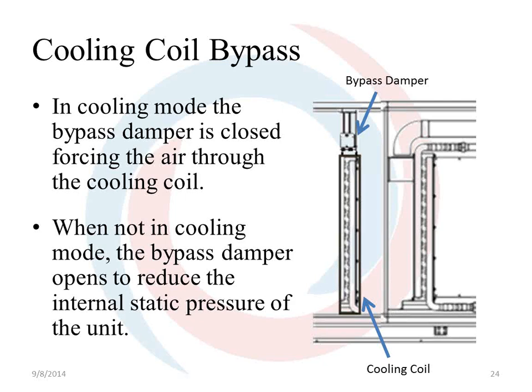Now the unit does come, or you can order as an option, a DX or chilled water coil. And what happens in the cooling mode, of course the air goes through the chilled water coil. In the heating mode, there's a bypass damper that opens up on top. So it bypasses the air into the heating coil. When that happens, there's less static pressure and the VFD can ramp the fan down. And that results in reduced amp draw and lower electrical operating costs.